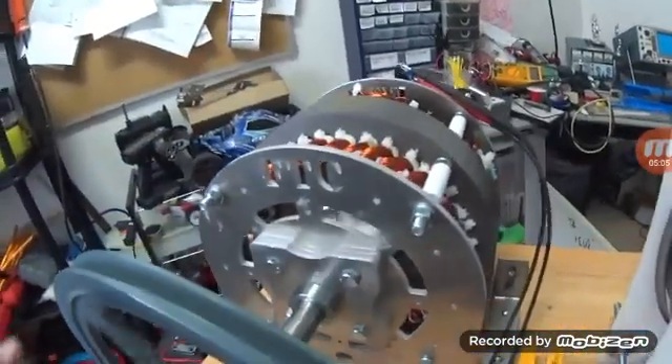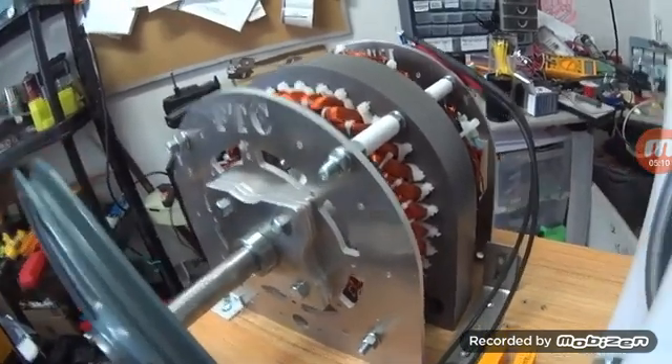Listen to it — that's not from shipping. Shipping is not going to loosen lock washers. The reason you use lock washers is because they prevent loosening under heavy vibration. So if they're loosening under shipping, don't even dare run the thing.